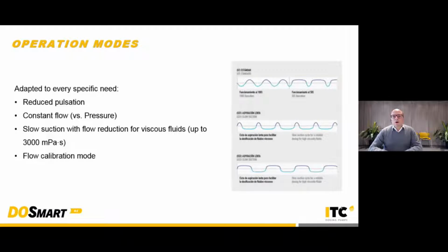We can work also on slow suction mode. This way, we can increase the viscosity of the flow of the fluid we are handling up to 3,000 millipascal seconds. This is a high viscosity product. To achieve this, we have to modify the profile for the suction and discharge, and this gives place to a reduction of the flow. We have 2 levels for this special configuration. In one of them, we reduce the flow to 70% of the nominal flow, and in the second one, which is the most convenient for high viscosity, the flow is reduced to 50%.